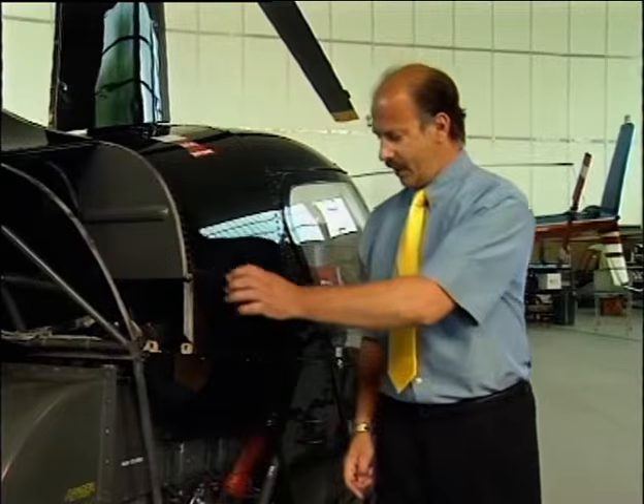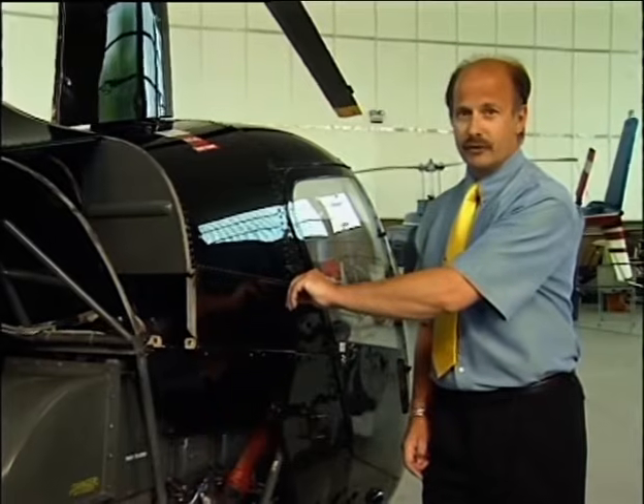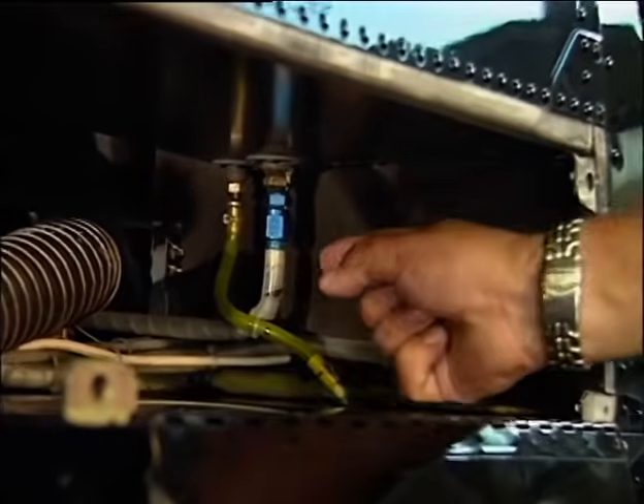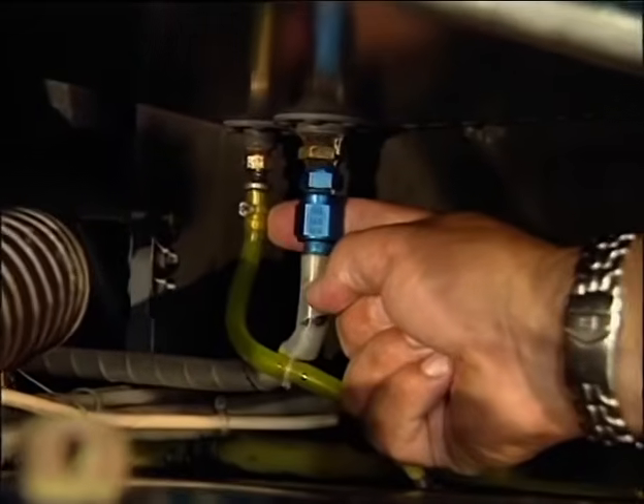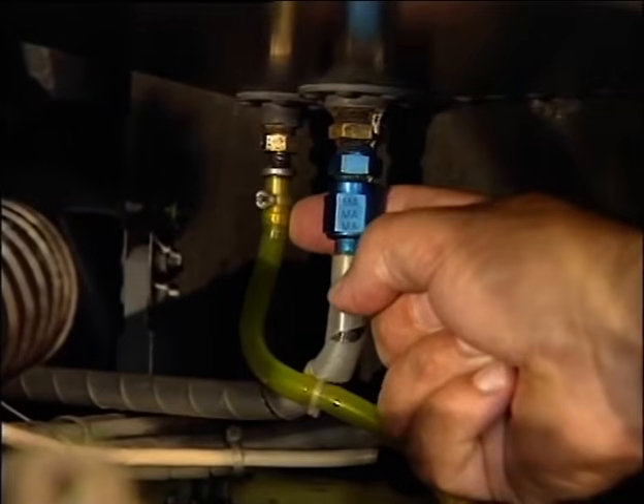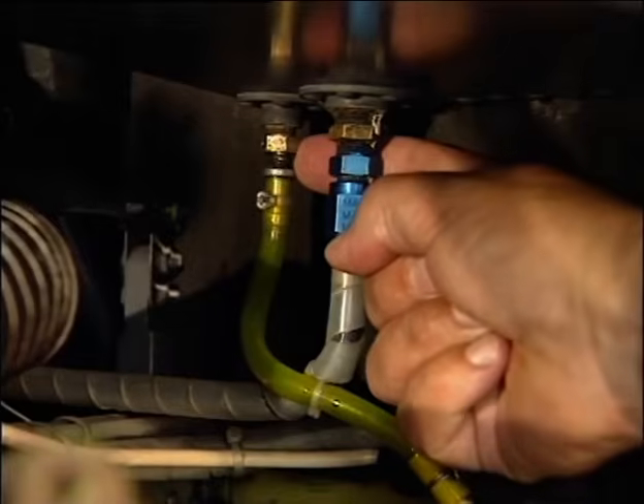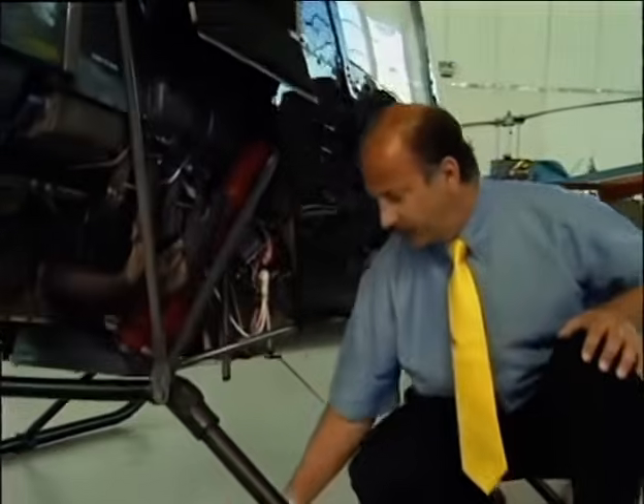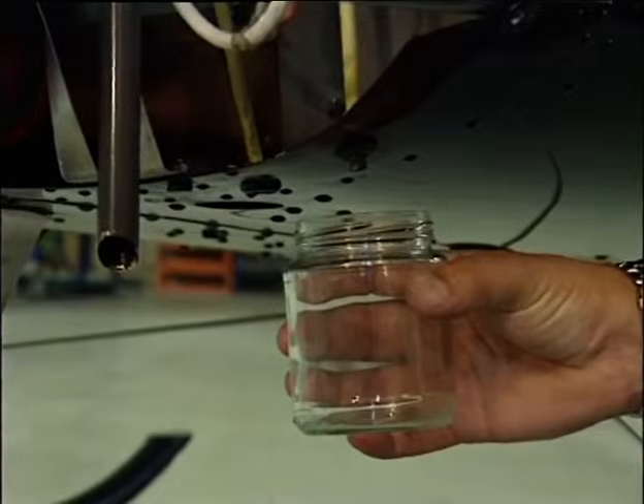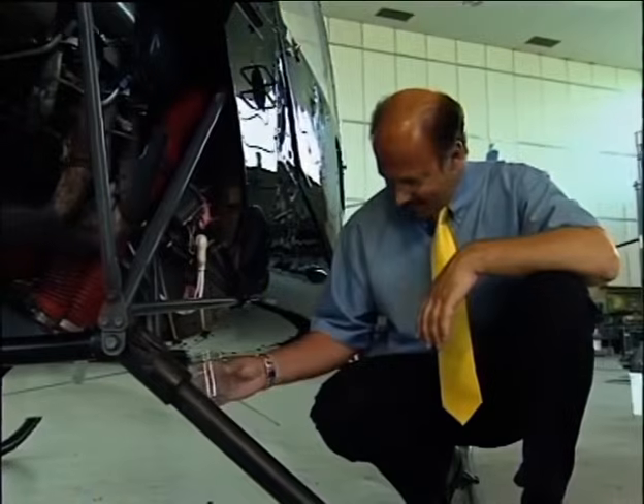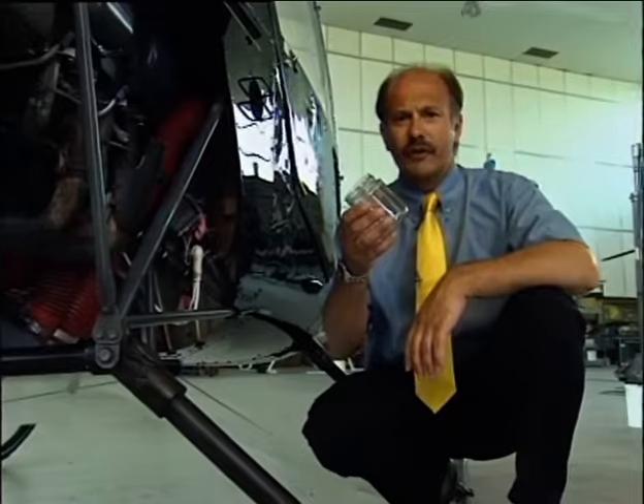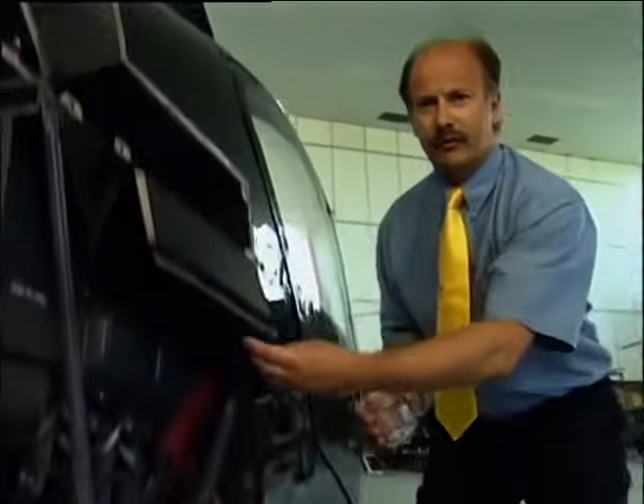We will now want to come down to have a look at the fuel sample check. Opening this panel gains us access to the auxiliary fuel tank drain, identified by this yellow pipe. Pushing up on this valve will allow us to take a sample in a suitably clean container from this position here. Having taken and checked the sample from the auxiliary tank, we need to do the same with the main tank.